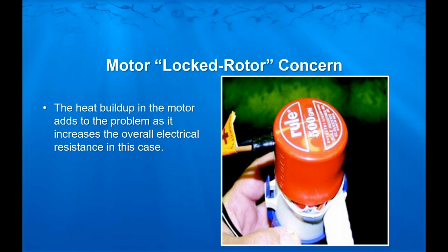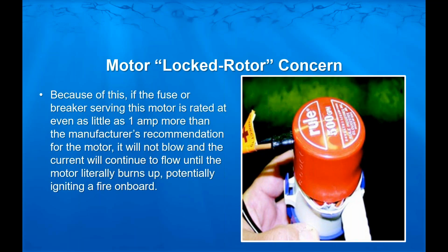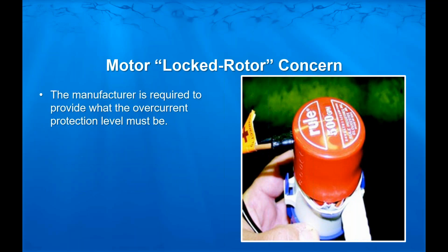Heat buildup in the motor is going to add to the problem because it's increasing the overall electrical resistance as it gets hotter. And because of this, if the fuse or breaker that's serving that motor is rated at even as little as 1 amp more than the manufacturer's recommended level for that motor, it's not going to blow, and the current will continue to flow until the motor literally burns up, potentially causing a fire on board. The manufacturers of motor devices are required to provide what the overcurrent protection level must be for that device in order for it to trip properly.